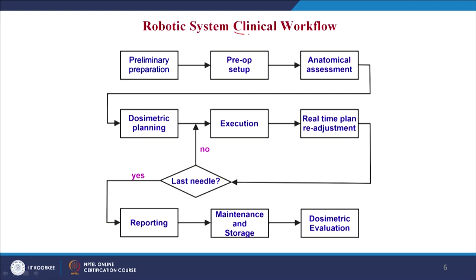Now come to the clinical workflow of the robotic system. The clinical workflow starts from preliminary preparation, which involves sterilizing the needling system, placing sterilized seeds in the sterilized cartridge, preparing the ultrasound machine connection to the computer, getting ready with the robotic system, and moving from rest to the initial posture of the robotic system. Then comes pre-operative setup, where we clean and disinfect the robot as well as the associated instrumentation in preparation for surgery.